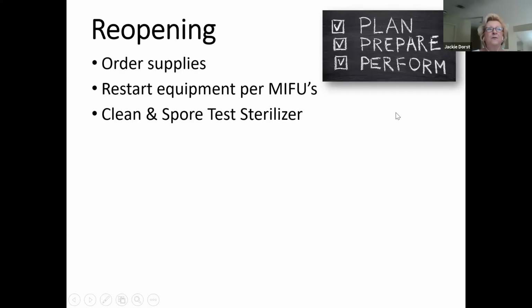You're going to have to check whether the seal or gasket has dried out, since those rubber gaskets can leak. So you need to start up, refill it, clean it, put fresh distilled water in it, and run a cycle and do a spore test on it.